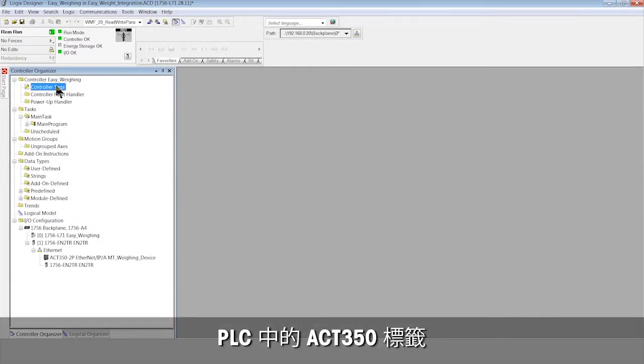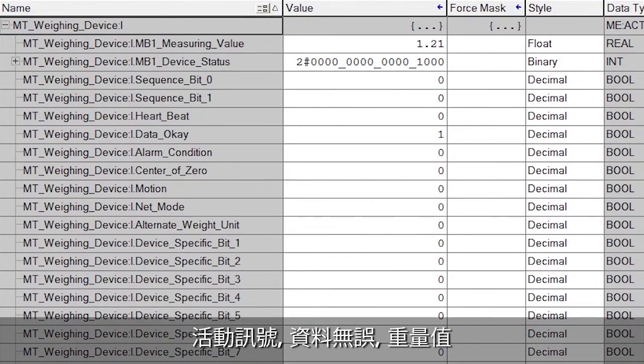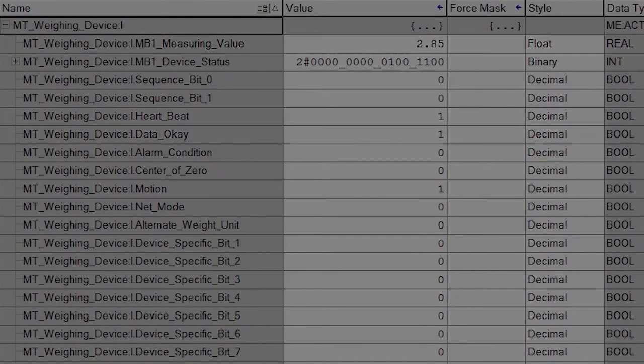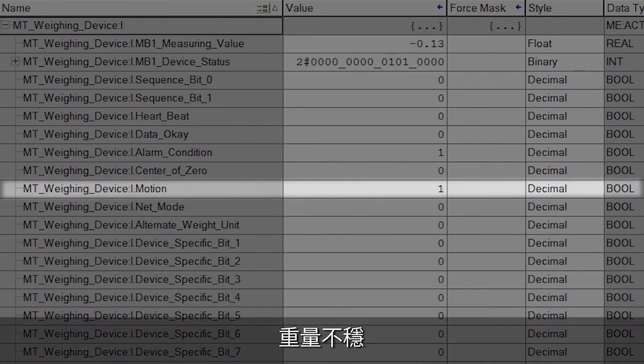We can now see the ACT350 tags in the PLC, including all status information: the heartbeat that shows connection, data OK bit and weight value. The alarm bit is on if any error such as underload is detected. The motion bit is on if weight is unstable.